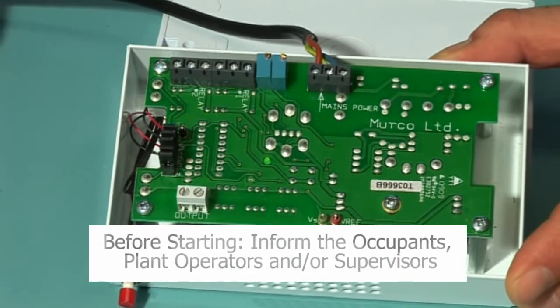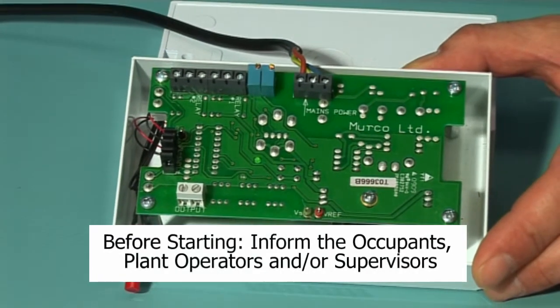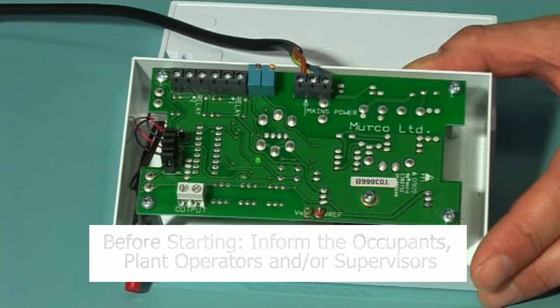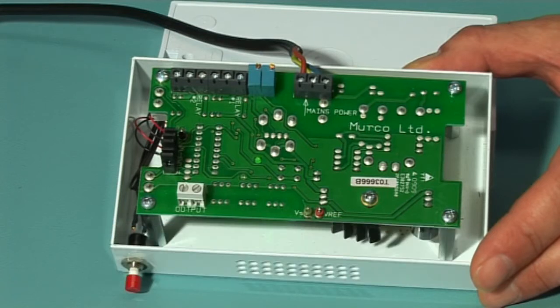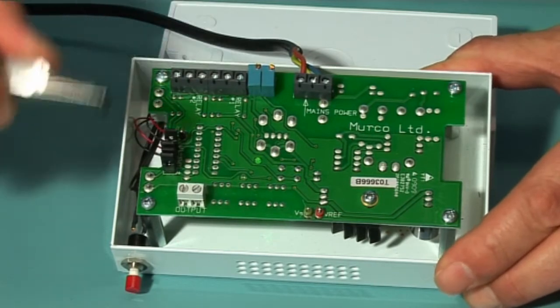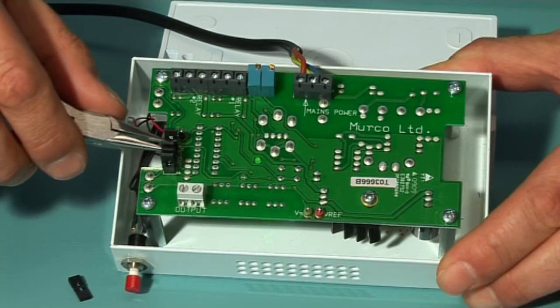Before starting, inform the occupants, plant operators and supervisors of the test. Check IAM connections to external equipment and disconnect if required. Deactivate any delays by removing jumpers one and two on HD1. Before performing your test, the IAM must be powered up overnight.